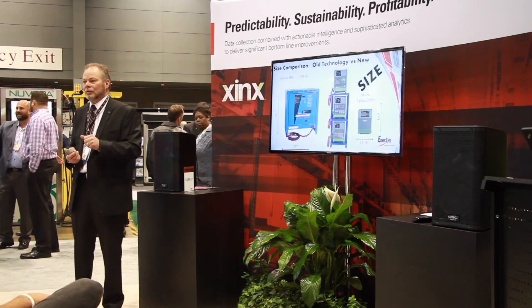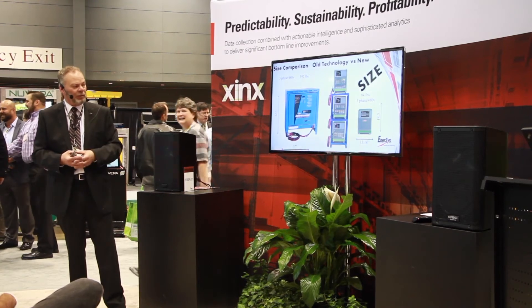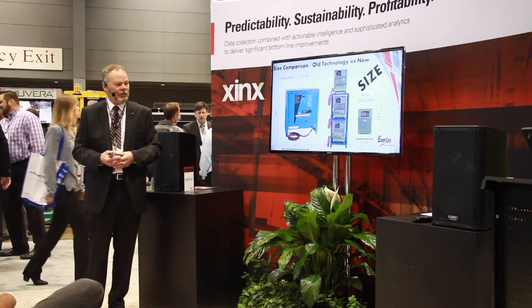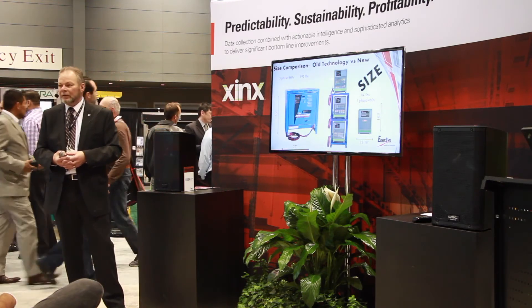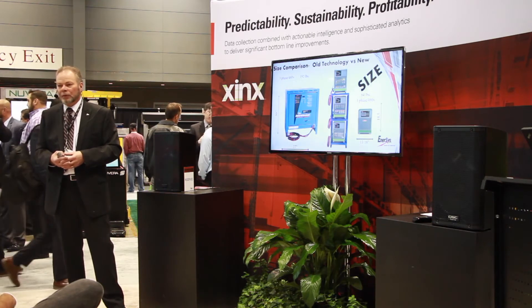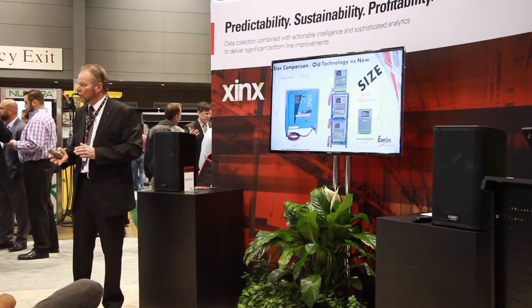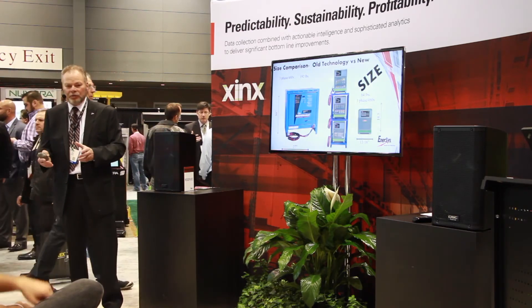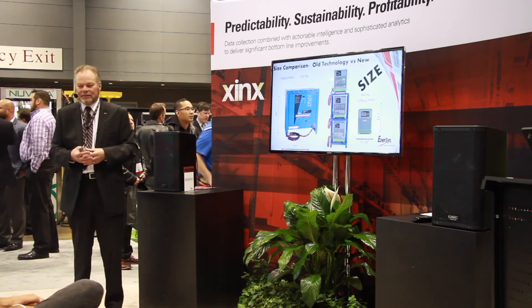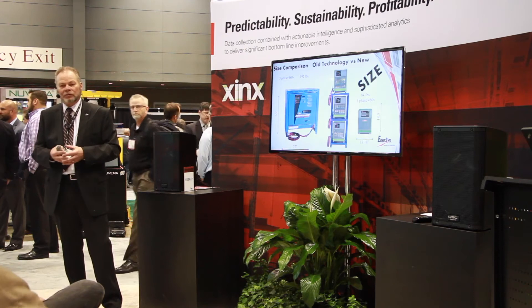Size has been reduced immensely. The old transformer-based chargers were about 30 inches by 27 inches — the industry-standard K1 spec. Today's charger is 18½ inches tall and 13½ inches wide; we could almost stack three of them in the same footprint height as the old unit. That makes for a very slim profile. With opportunity and fast charging becoming big in our industry, I now have a charger that weighs 84 pounds — I can hang it on a column, put it on the wall, almost anywhere — making it easy to locate throughout the building for opportunity or fast charge applications.